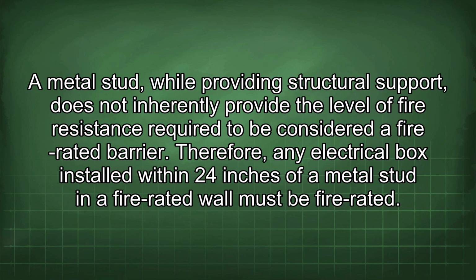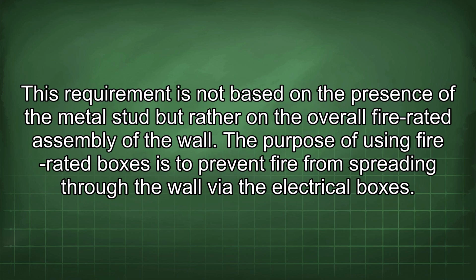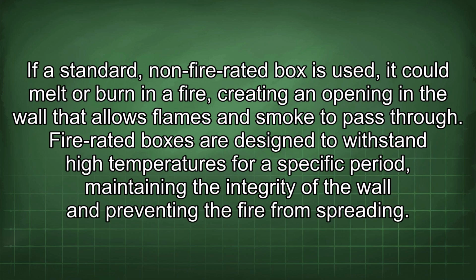Therefore, any electrical box installed within 24 inches of a metal stud in a fire-rated wall must be fire-rated. This requirement is not based on the presence of the metal stud but rather on the overall fire-rated assembly of the wall. The purpose of using fire-rated boxes is to prevent fire from spreading through the wall via the electrical boxes. If a standard, non-fire-rated box is used, it could melt or burn in a fire, creating an opening in the wall that allows flames and smoke to pass through.